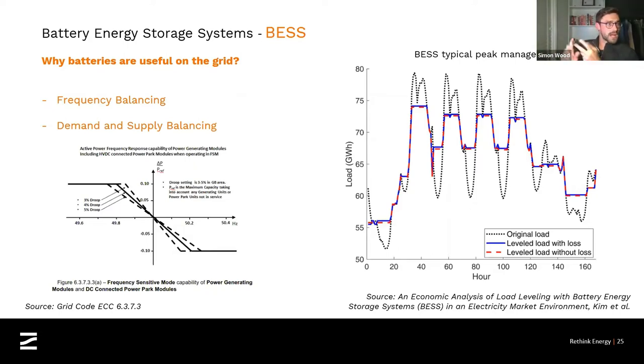I think it was a large wind farm and maybe a gas station that tripped, or I think the wind farm tripped first, and that subsequently caused the gas CCGT to trip. Ultimately, grid stability dropped off a cliff, and you suddenly got a domino effect of assets tripping off and protection systems kicking in. That's why we saw the blackouts. Ultimately, that was a system response to frequency falling and systems being shut down. So if we'd had hundreds of megawatts of batteries connected on the system doing frequency response at that point in time, we might have been able to stop those blackouts. That's the kind of thing that battery storage technology is looking to support as we move to this newer energy mix.